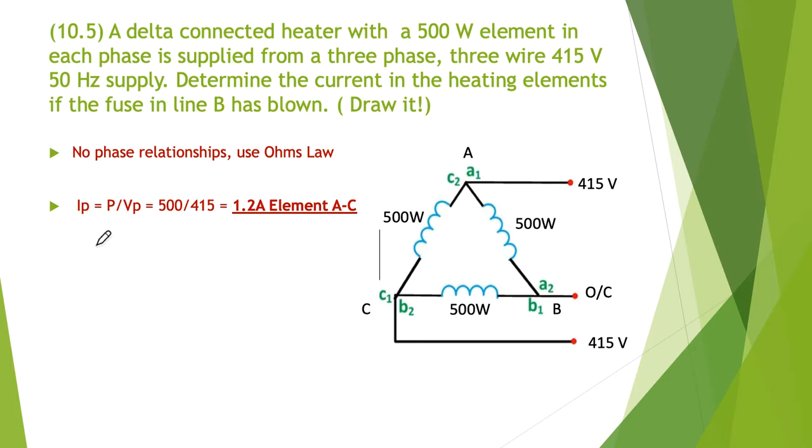And the first thing we can determine is the IP. The IP is the power divided by the voltage. Now we know the voltage is 415. So if to find out what the current is, the current is simply the power in the phase. So we know the phase power is 500 divided by 415 volts. And that works out at 1.2 amps through elements A to C.